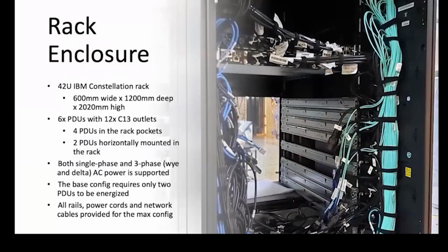Now, for completeness, we can take a look at the rack enclosure where all these components are put. It's a 42U IBM Constellation rack, 600 millimeters wide, 1,200 millimeters deep, and 2,020 millimeters high. It has 6 power distribution units. Each of them has 12 C13 outlets for plugging in the components. The PDUs are basically put 4 in the rack pockets and 2 horizontally mounted up near the top of the rack. So there's lots of places for all the components to be plugged in.